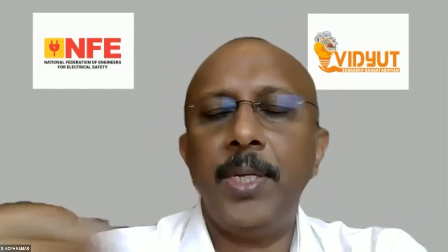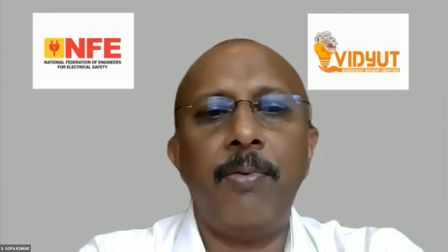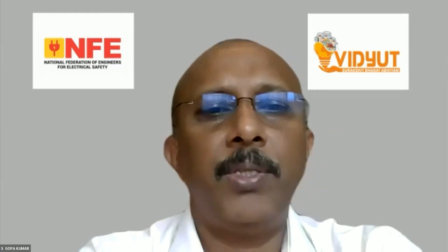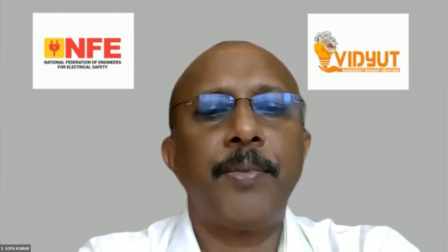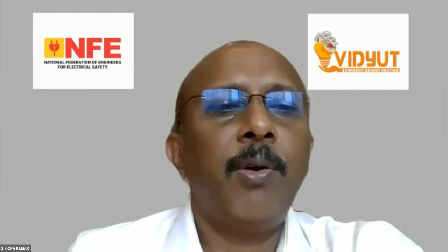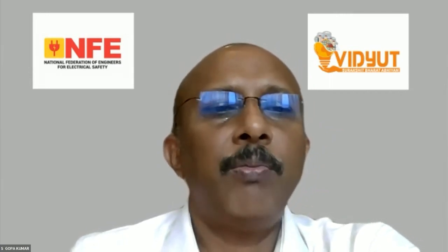Is NEC mandatory in case of violation? What will be the action taken, and by whom? Question by Mr. Imran Maulavi. Mr. Imran, you must understand the safety regulations of the Government of India, called the CEA, Central Electricity Authority, measures relating to safety and electric supply. An amendment is going on. The new regulation 14, sub-regulation 2, says that any subject which is not included in the regulation, the National Electrical Code of India shall be followed. Now, the regulation talks mainly about generation, transmission, and distribution. Of course, something is also included for an installation.